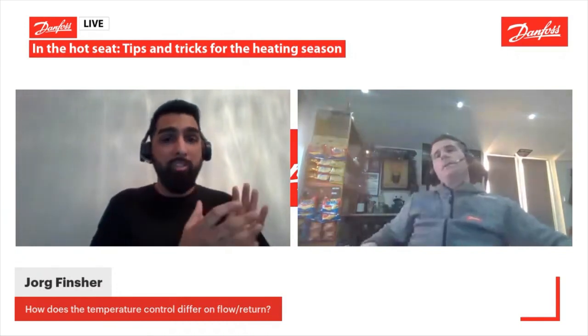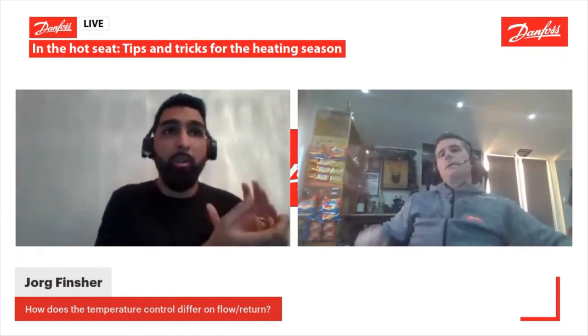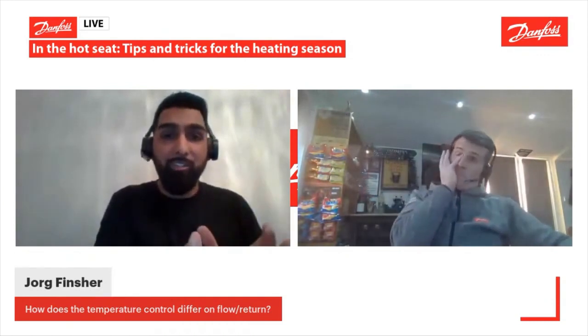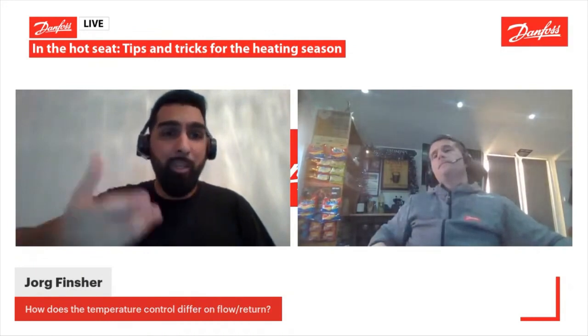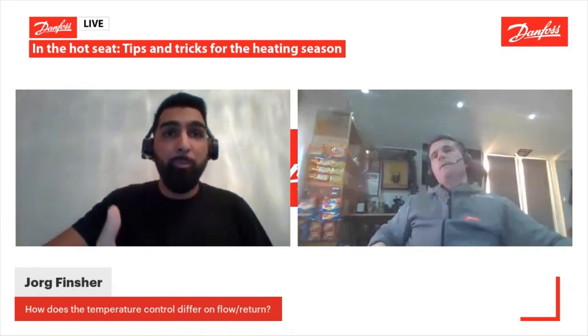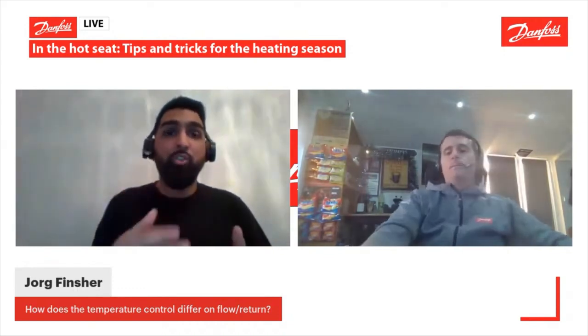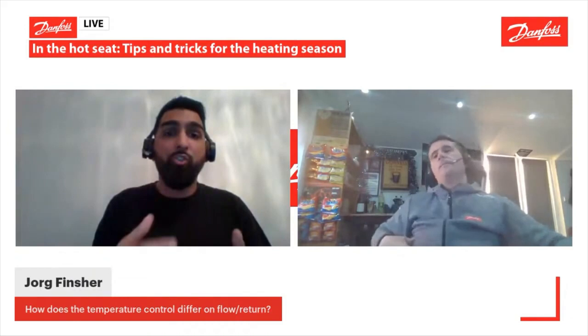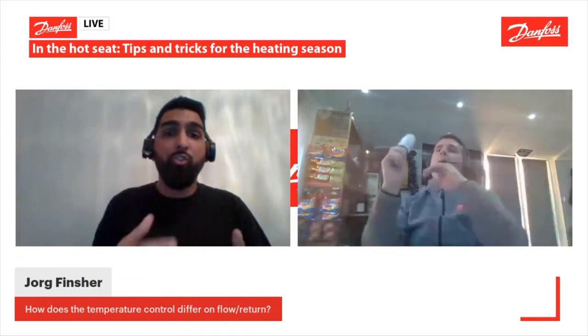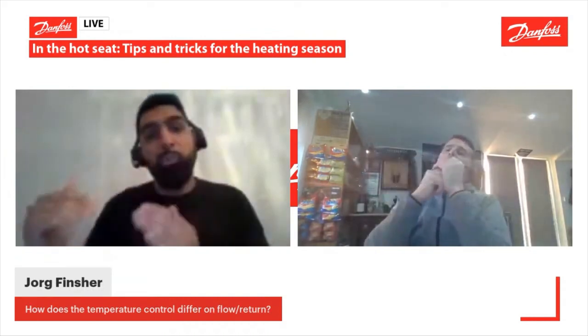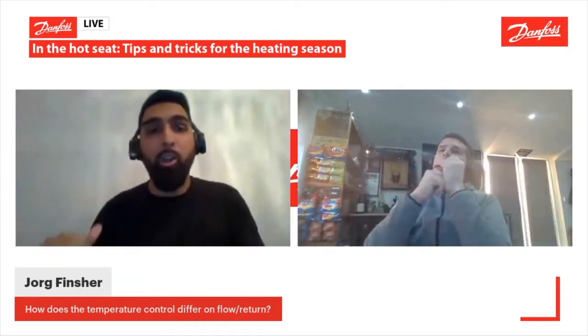What happens is when that temperature of water reaches the radiators, which is your heating emitter, a lot of the heat should be dissipating. A lot of heat should be being released from the radiators. Okay, so when it's being released from the radiators, what we're actually trying to do is we're trying to release approximately 20 degrees Celsius of that heat out into the atmosphere. So our return is 20 degrees Celsius lower.